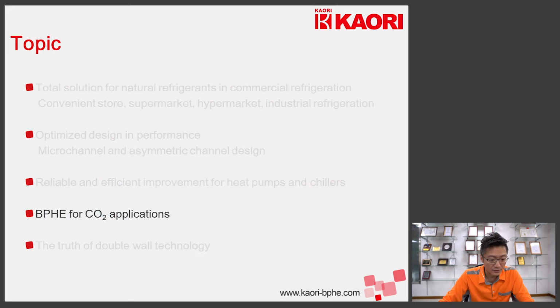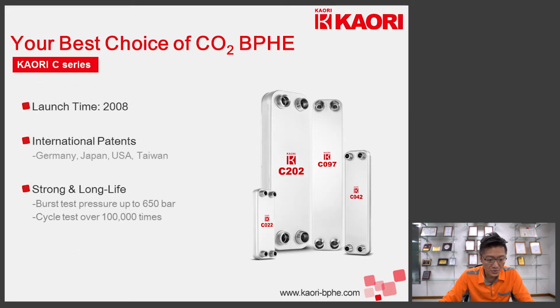And in this topic, let's look at brazed plate heat exchangers in CO2 applications. The characteristic of CO2 is its high working pressure, and we need to have a strong and robust unit to cope with this pressure requirement. First of all, Kaori is not new in CO2 applications. The C series for CO2 was launched back in 2008, and it received many patents in major regions of the world. And they are constructed in a robust and muscular way, so the burst pressure is over 650 bar. And we also run cycling tests from 0 to 140 bars with over 100,000 cycles.